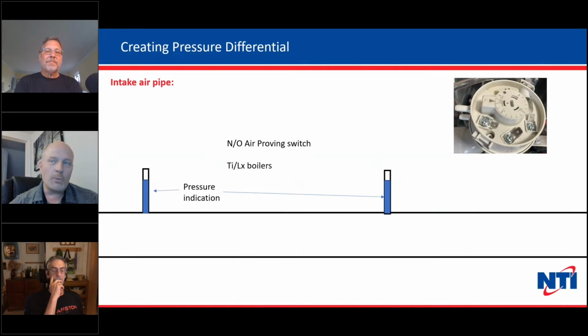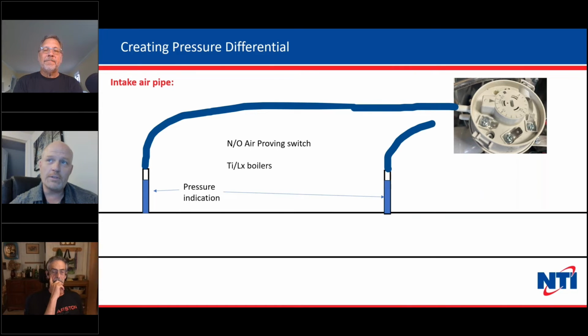So the way we get around that, and the way we're able to use this as an air proving switch, is we actually place an artificial restriction in the intake pipe. So we're going to run our tubes first. There's our air tubing connected. And these two little blue blocks in the middle here, that creates an artificial restriction. And just like if you've ever washed your car with a garden hose and you're going around the back of the hose and you start tugging on it, all of a sudden it kinks. Anything after the kink loses water pressure. Well, the same thing happens when air flows through this pipe.